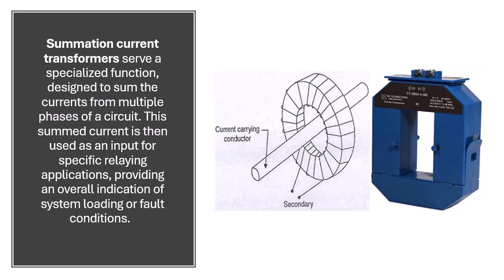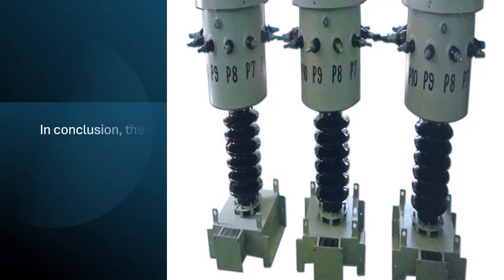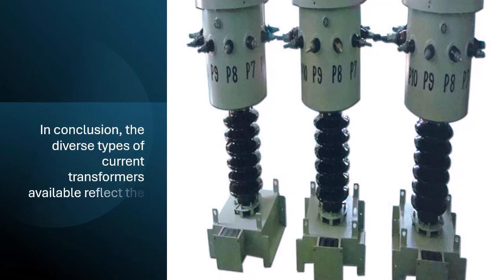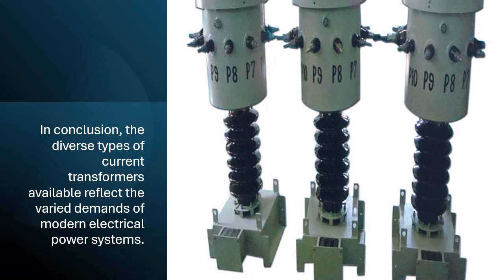Their primary role is to provide signals to protective relays, enabling the swift isolation of faulty sections of the power system. Summation current transformers serve a specialized function, designed to sum the currents from multiple phases of a circuit. This summed current is then used as an input for specific relaying applications, providing an overall indication of system loading or fault conditions.